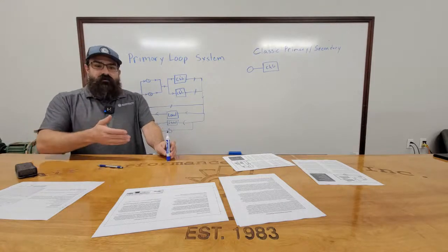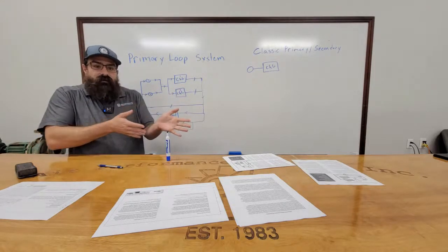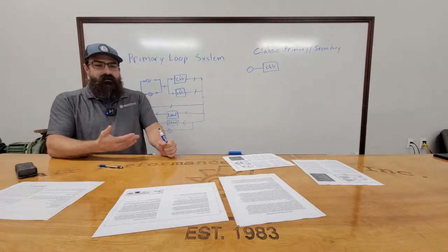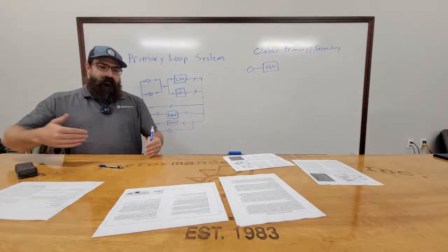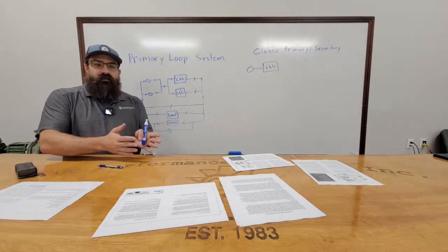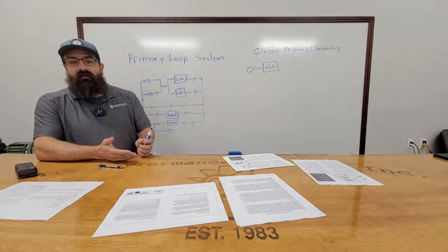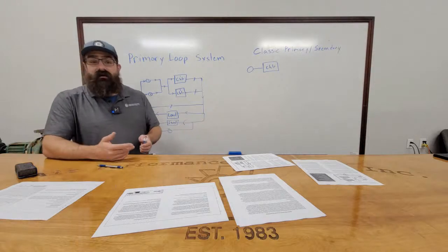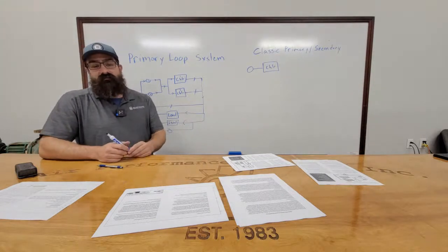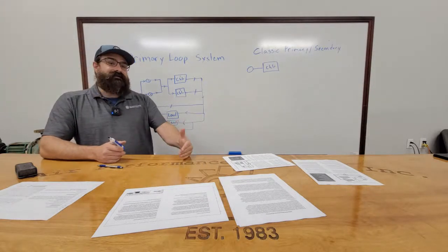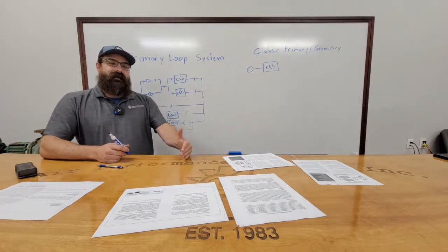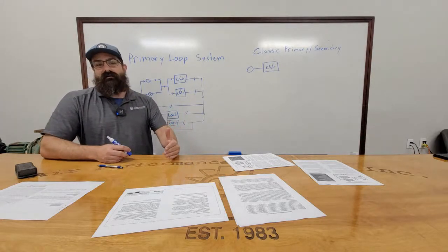Water only fits so much water in a tube. You can't compress water like you can air. So you can only fit so much water. So the only thing you can do is increase the amount of pressure or head you're putting on the water, basically tricking the air handler. It's still not running at its most efficient rate. Even though it has the 18 PSI we need on six, it still doesn't technically have the flow and the pressure it needs.